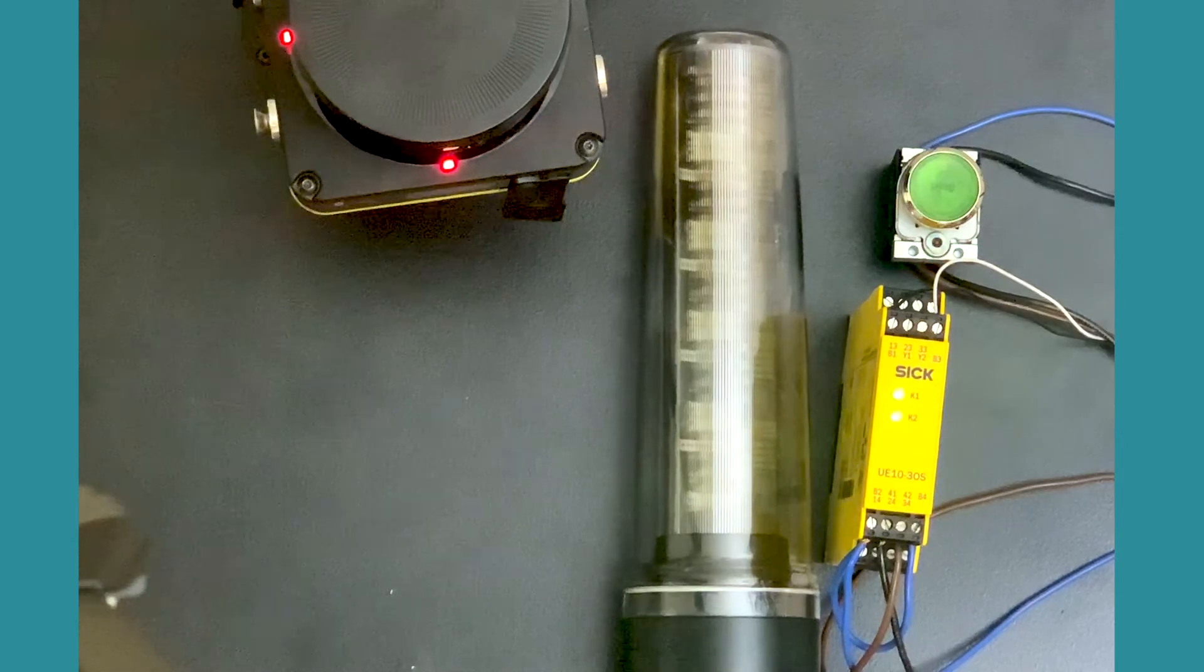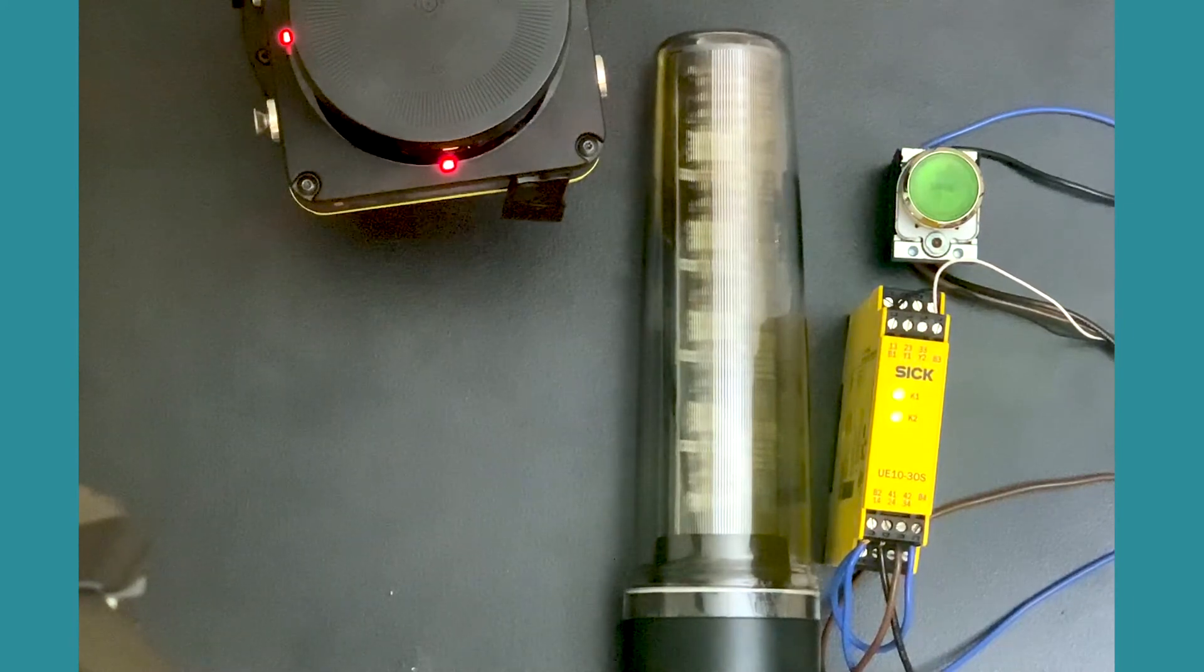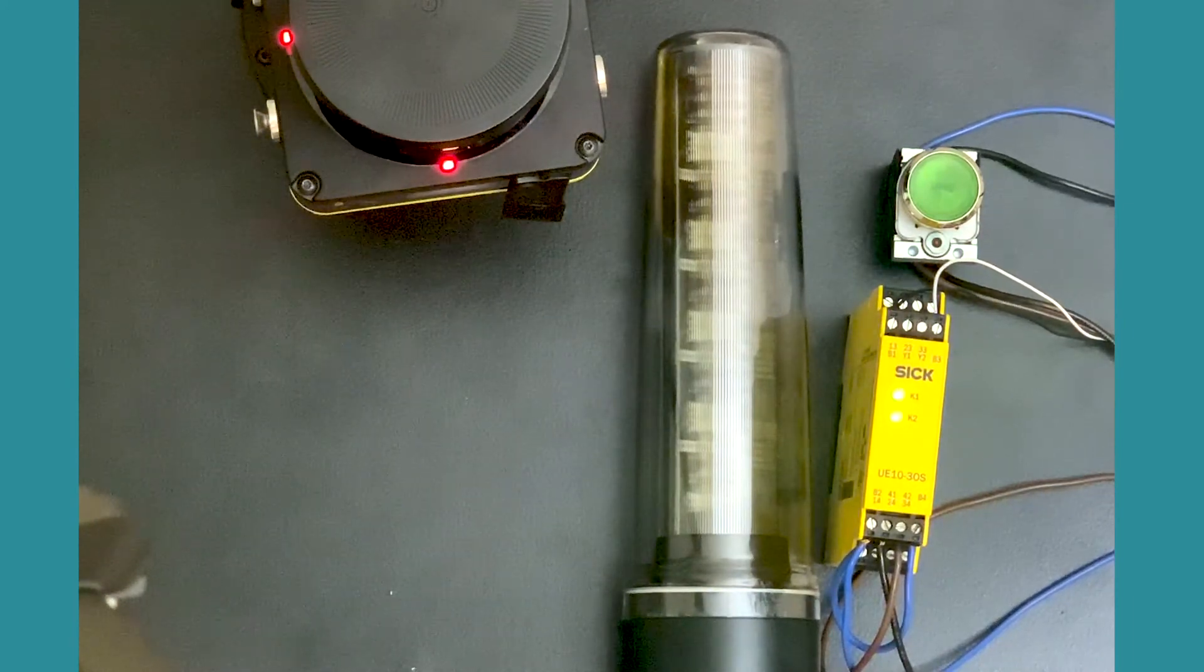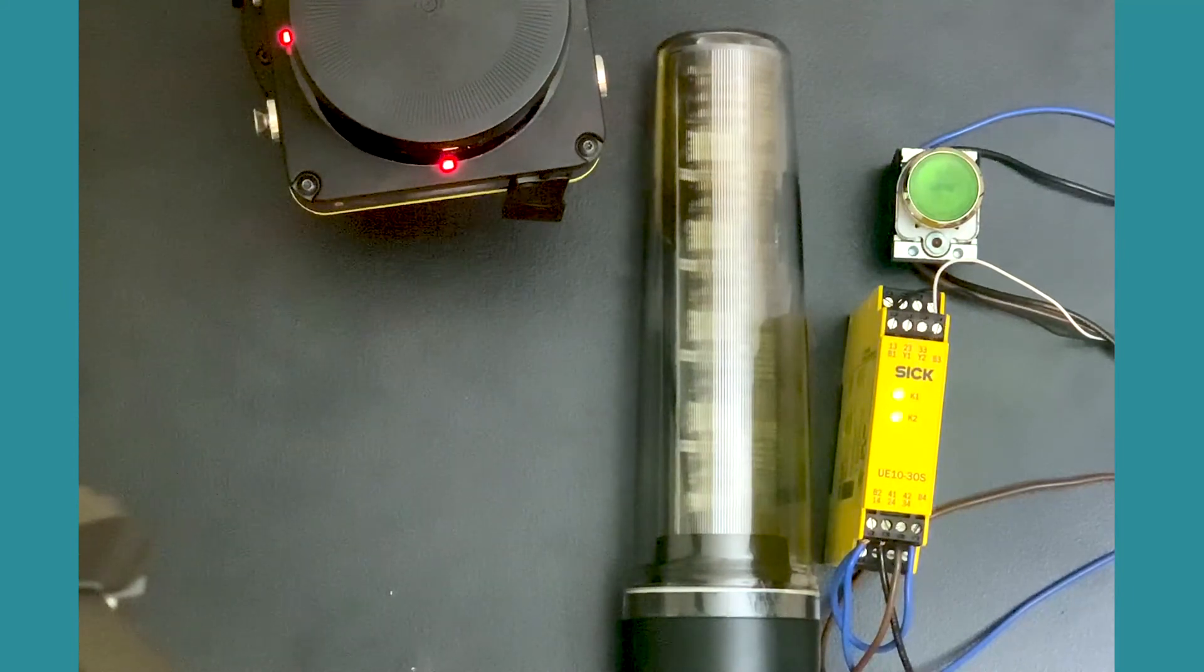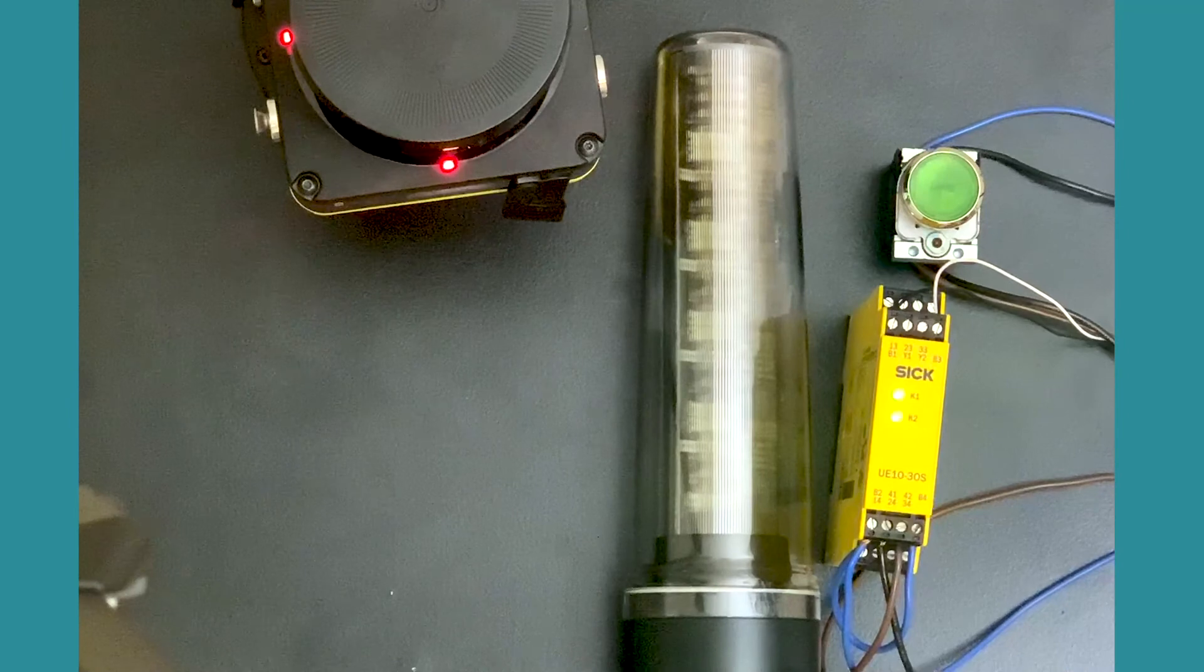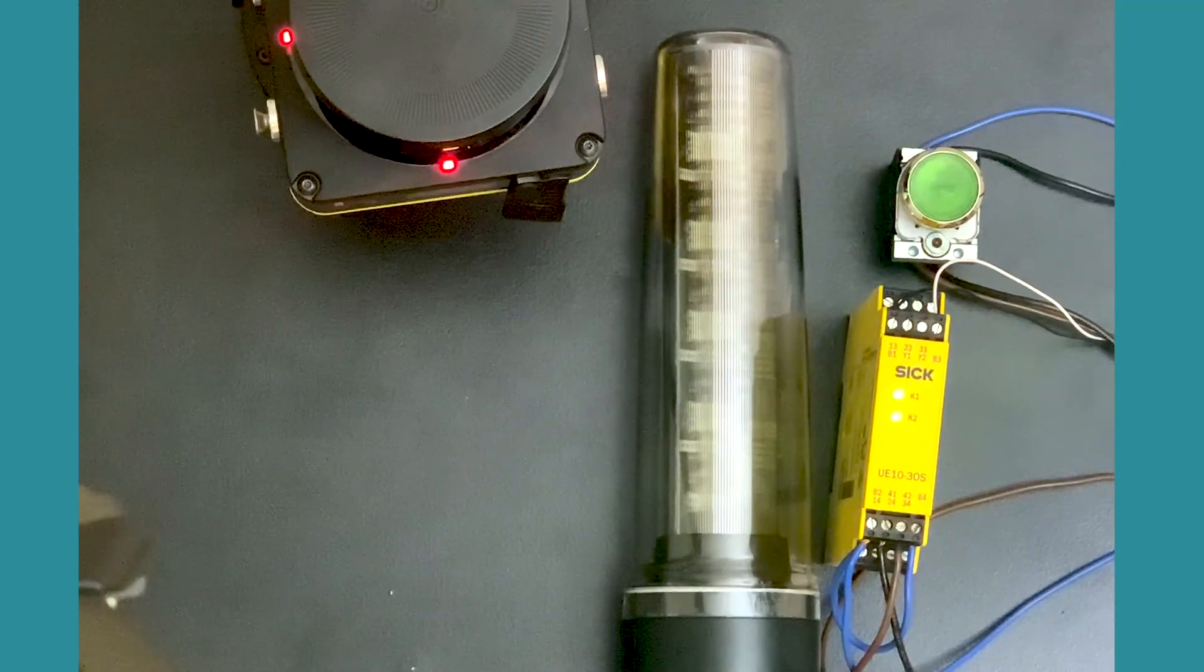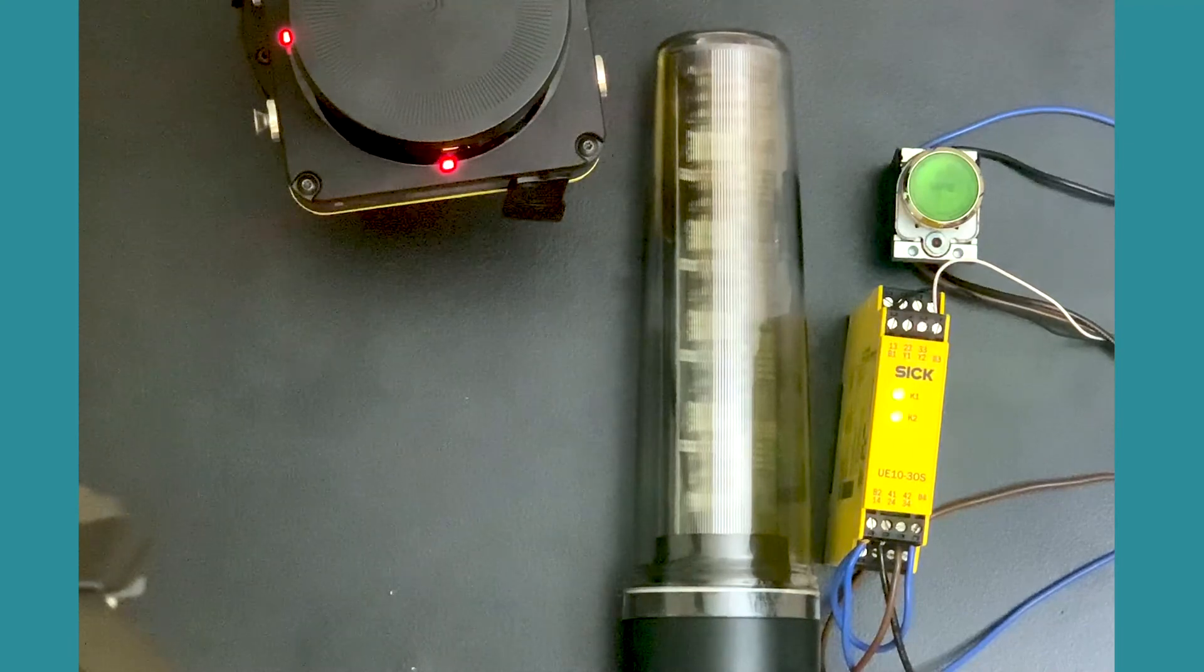We have the final demo ready. The scanner is monitoring the protective field as well as the warning field, and it is hooked up to the reset button, a relay which currently is energized, and a signal tower. The signal tower here represents the functioning of the robot.